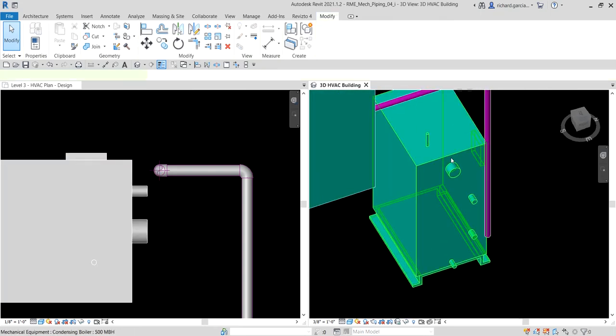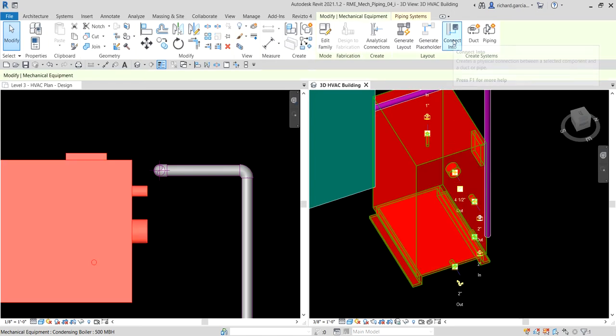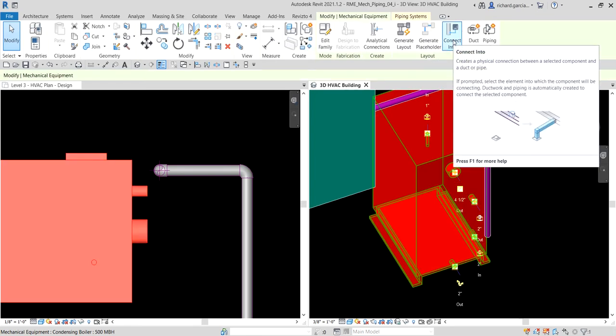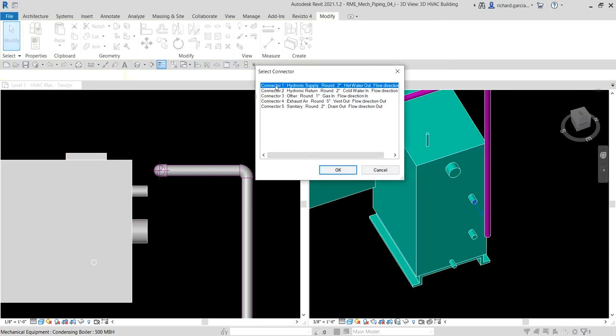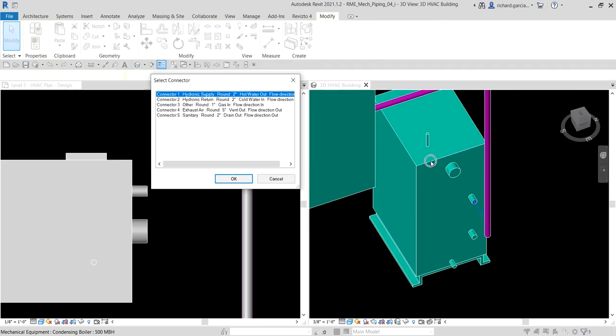I'm going to select the boiler and use the Connect Into tool, which creates a physical connection between a selected component and a duct or pipe. It will show me the connectors available on this boiler — we have five: hydronic supply, hydronic return, another connector for gas, for exhaust air, and for sanitary. We use Connect Into on components with connectors to automatically create piping between the component and the existing system, and this tool automatically creates the appropriate fittings.